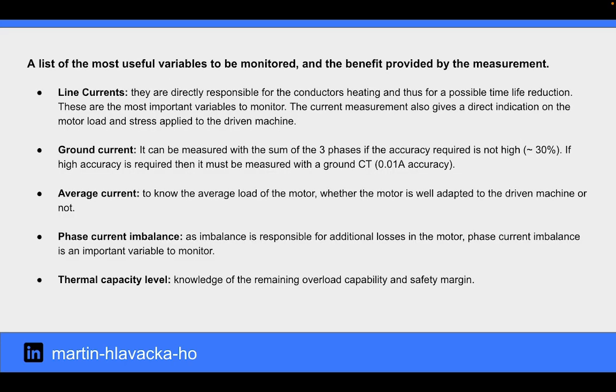Here is a list of the most useful variables to be monitored and the benefit provided by the measurement. Line currents are directly responsible for the conductor's heating and thus for a possible lifetime reduction. These are the most important variables to monitor. The current measurement also gives a direct indication of the motor load and stress applied to the driven machine.